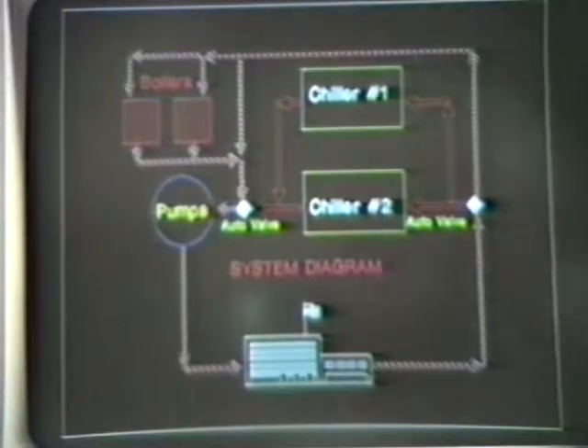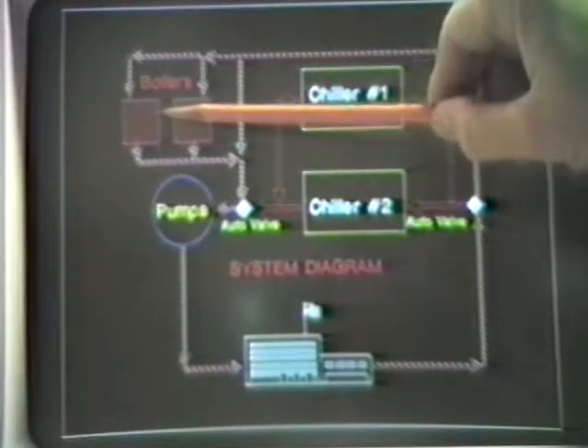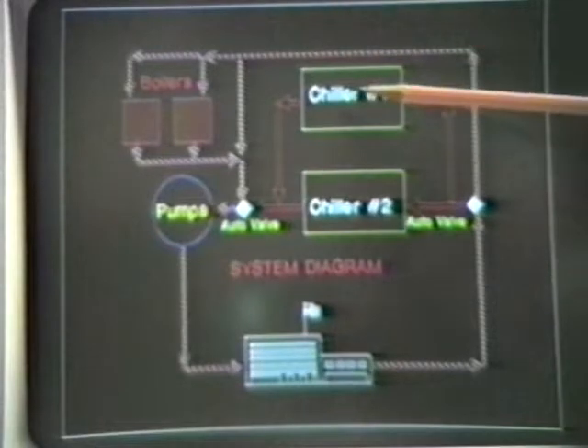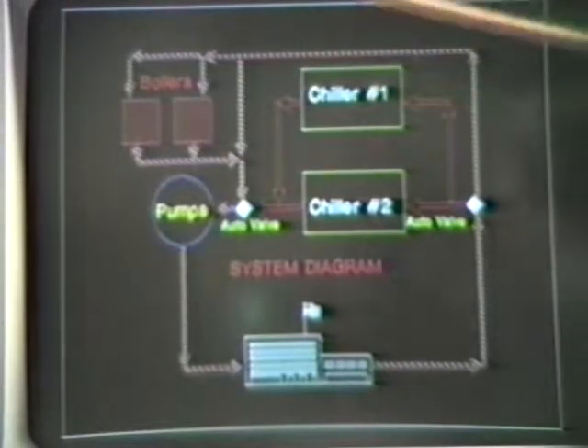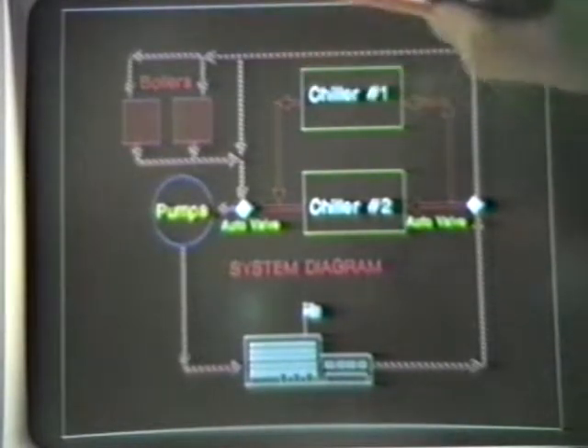The systems change over automatically, but I would like to take a second here to explain how important it is to allow enough time from changeover from heating to cooling or vice versa. There are controllers that sense the water temperatures that will not allow hot water to be put into the chillers or too cold of water from the chillers to be put into the boilers.